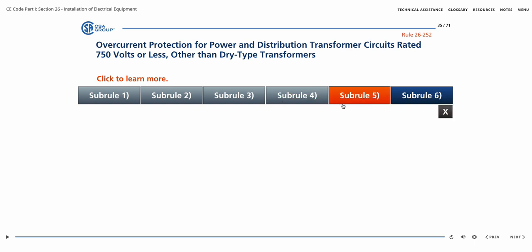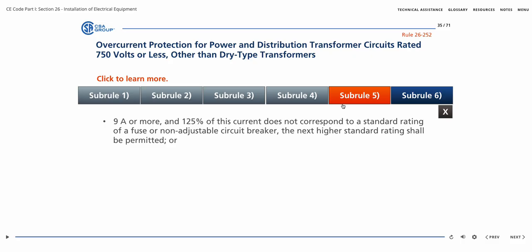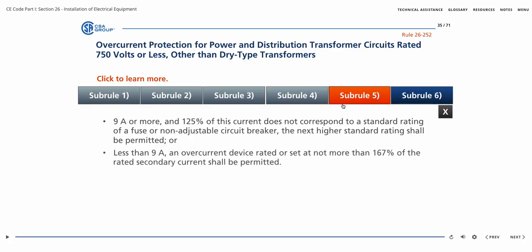Where the rated secondary current of a transformer is 9 amps or more, and 125% of this current does not correspond to a standard rating of a fuse or non-adjustable circuit breaker, the next higher standard rating shall be permitted. Or, if less than 9 amps, an overcurrent device rated or set at not more than 167% of the rated secondary current shall be permitted.